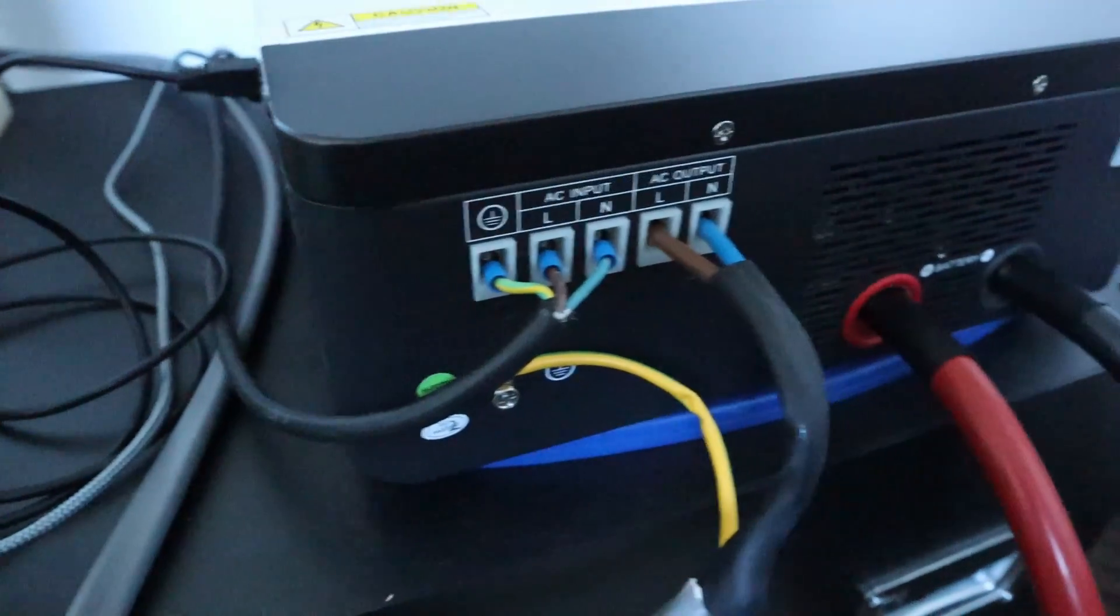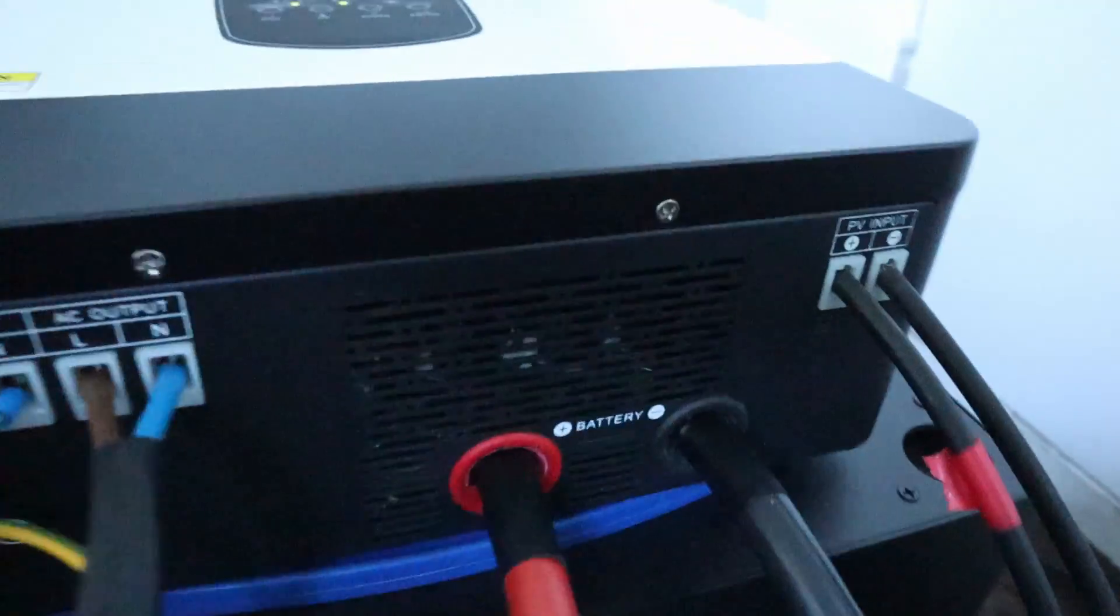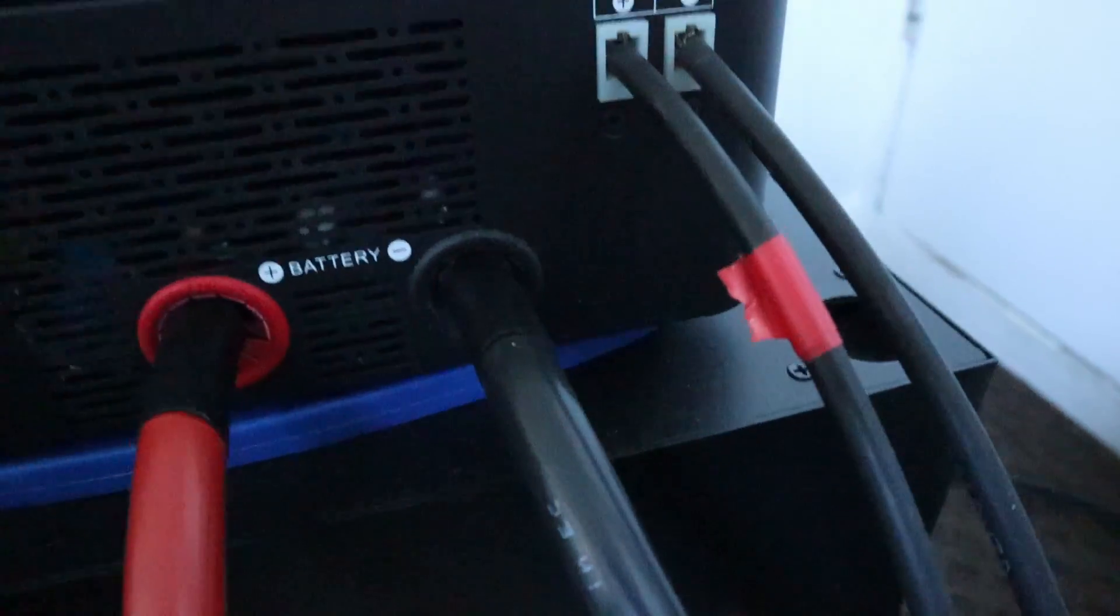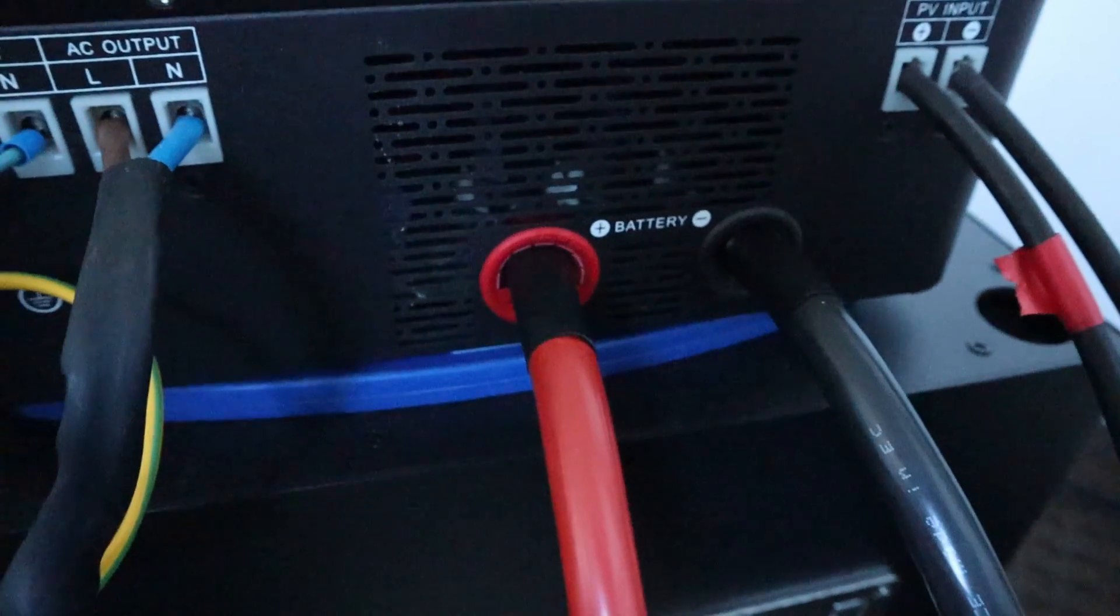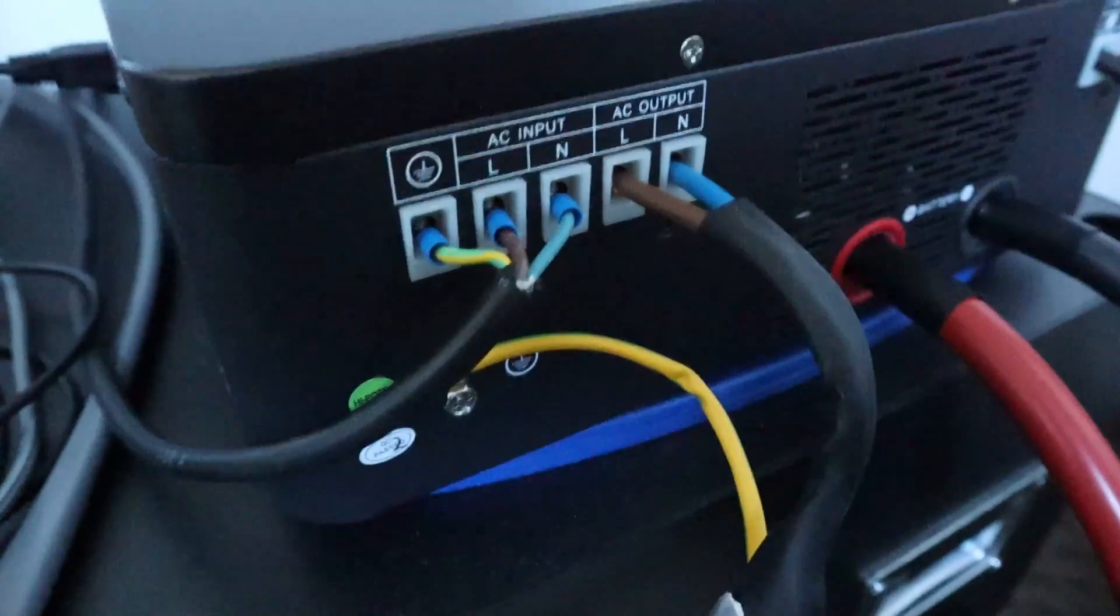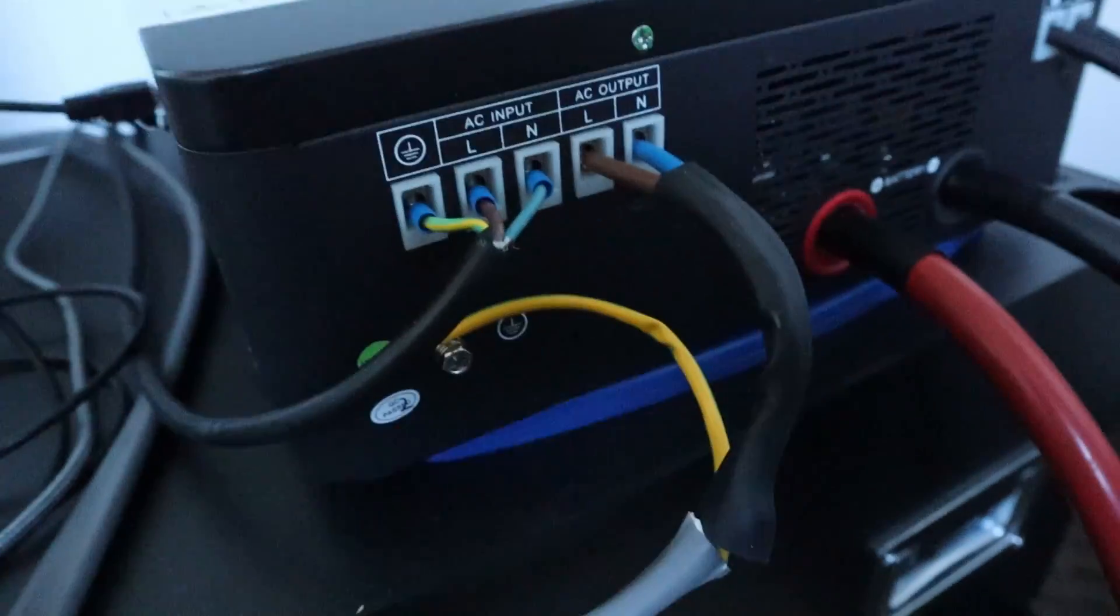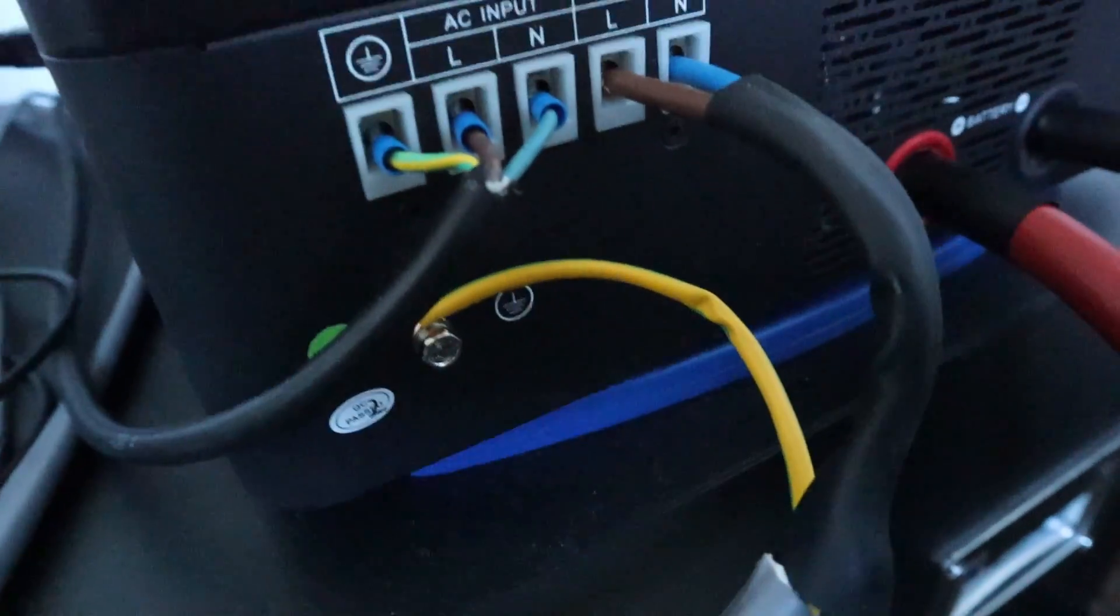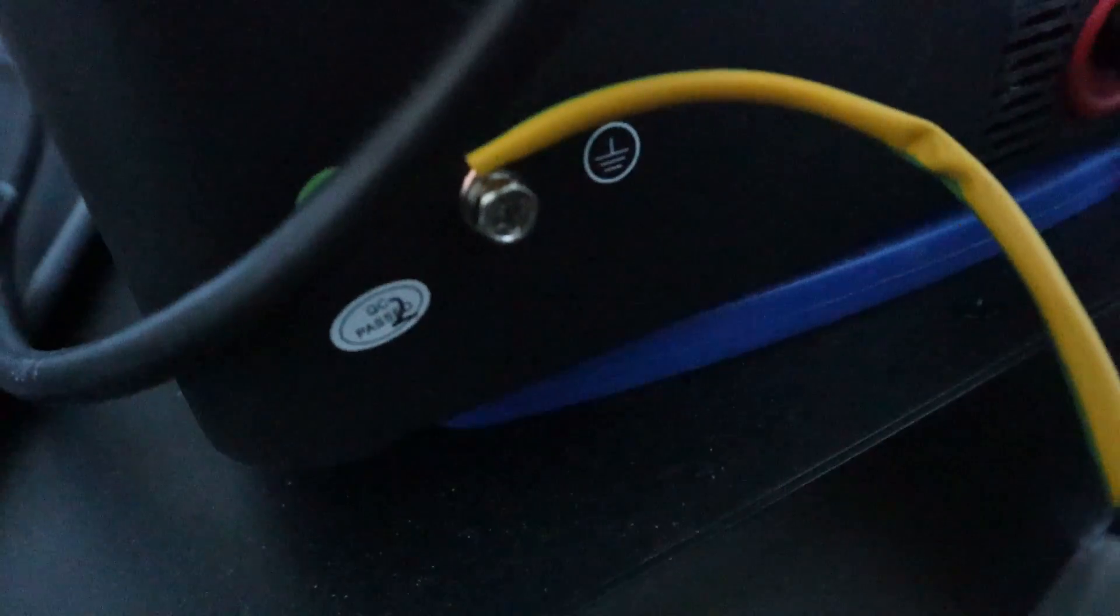I've got the same setup, it's pretty much the same box as the 24 volt version. The PV comes in there, I've marked up the positive one. I've got the two battery cables. I've used some 6 millimeter squared twin and earth cable here. I've put a bit of heat shrink around there to keep it neat and tidy so the cables aren't individual. I've had to strip it back so I can put the earth sleeving on and connect up the earth as well.